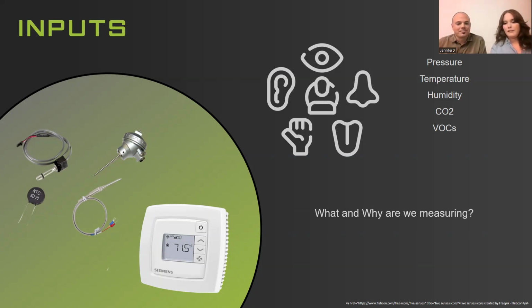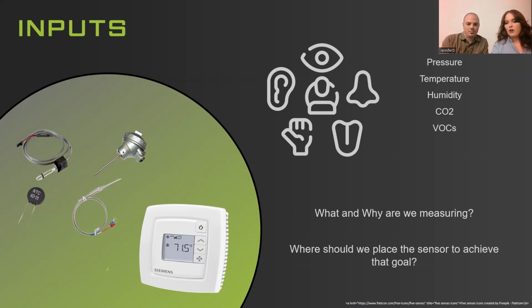And then we move on to where. Where something goes is also just as important. So if you were walking into a giant room and there was a wall of windows, where logically would you think you should be putting your temperature sensor? Right by the window? That would be wrong. It would be somewhere in a space that's a little bit more even, because you want to make sure you're picking up the true temperature of the space where people are going to be moving around, working, doing what it is they need to do, instead of putting it right next to a window where there might be direct sunlight coming through.